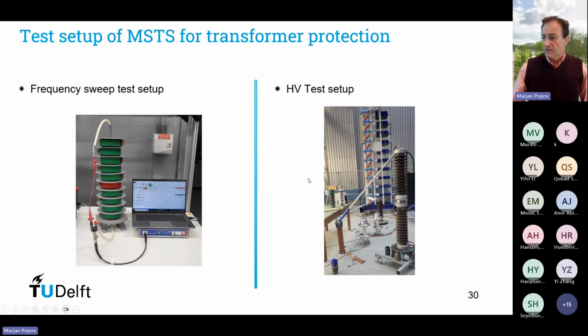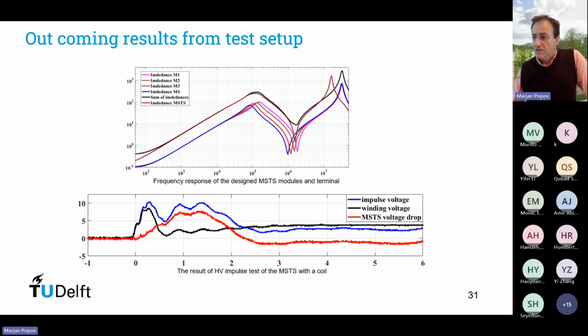This is how the frequency sweep test was conducted in the high voltage lab at TU Delft. This is the prototype of the device, and this is our high voltage lab where we tested this device by applying lightning impulse. In the results in this graph, the blue line shows the lightning impulse. The black line shows the voltage at the transformer terminals. And between the source and the transformer is the voltage drop on the device.